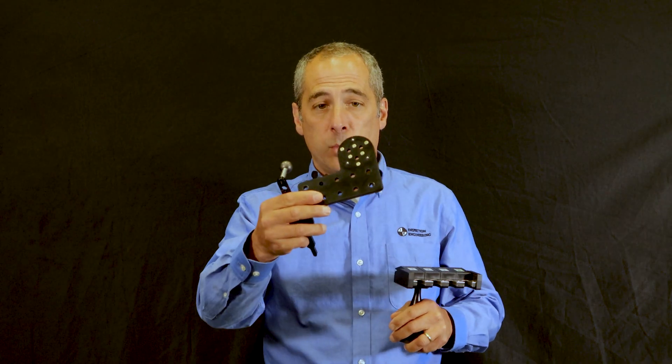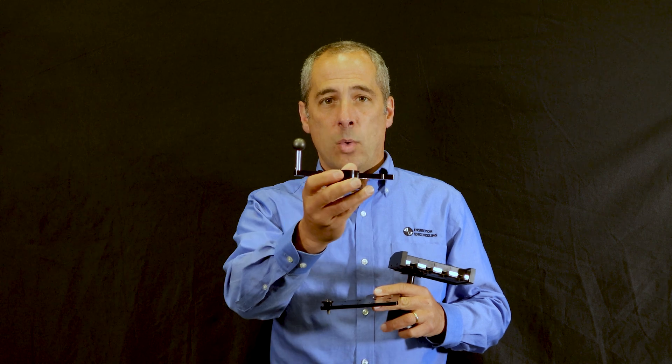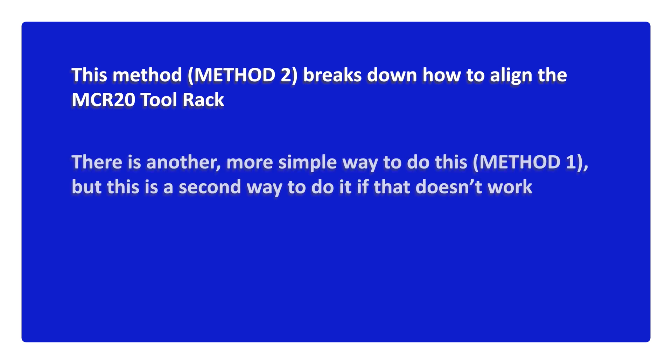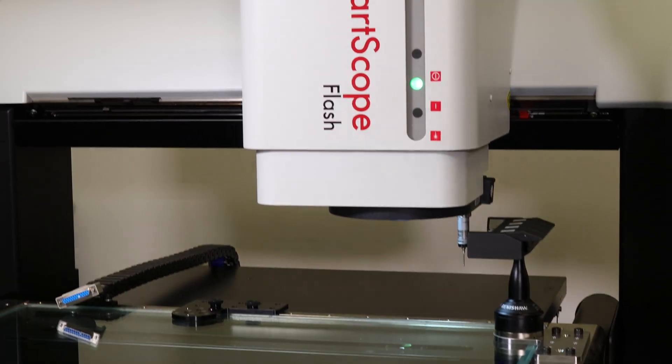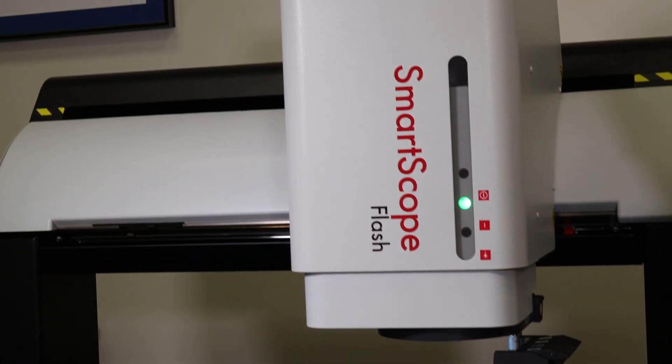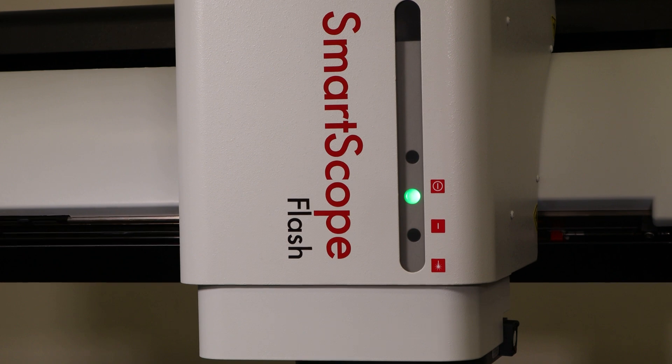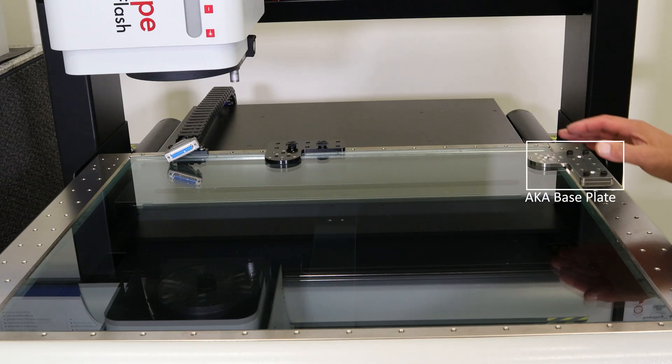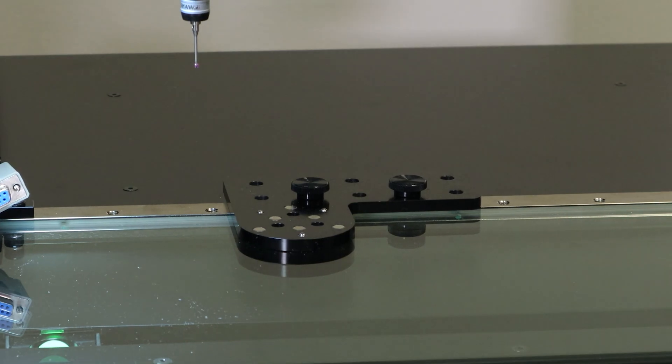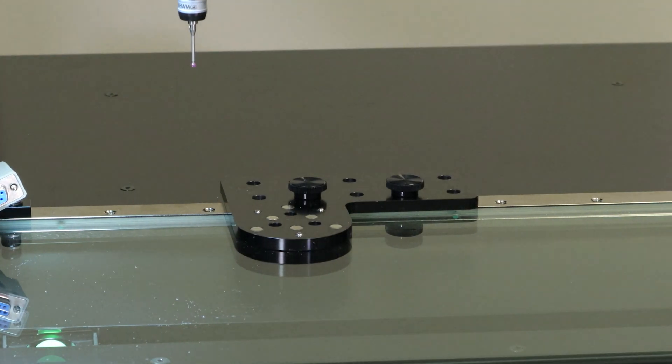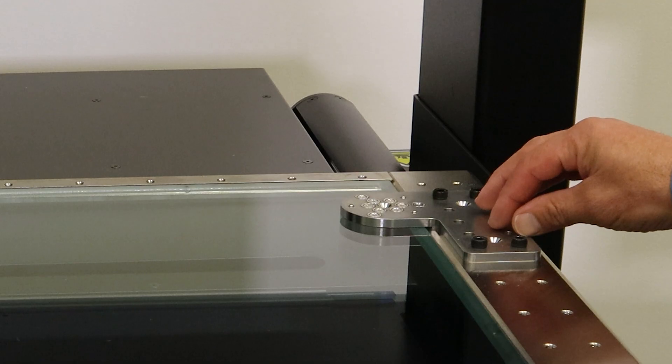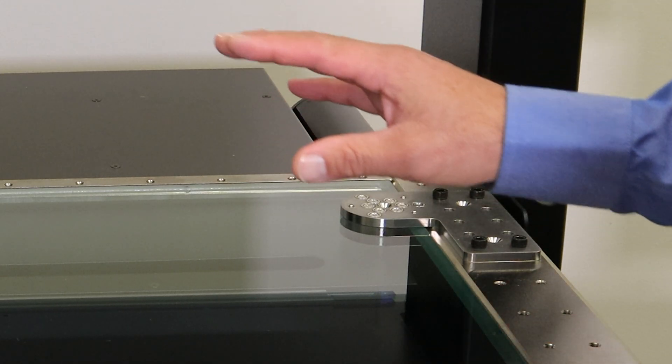Today we're doing our demonstration on an OGP Flash SmartScope, model 500, a little bit bigger table than many machines. This machine is equipped with two different kinematic mounts: the black one is the older style with magnets, and the newer style is the stainless steel system with extra magnets. Either one will work, but you will need at least one.